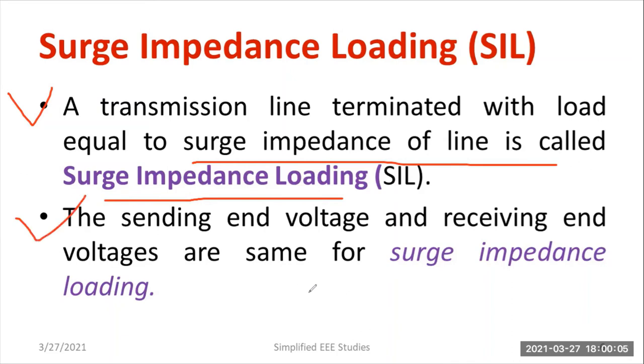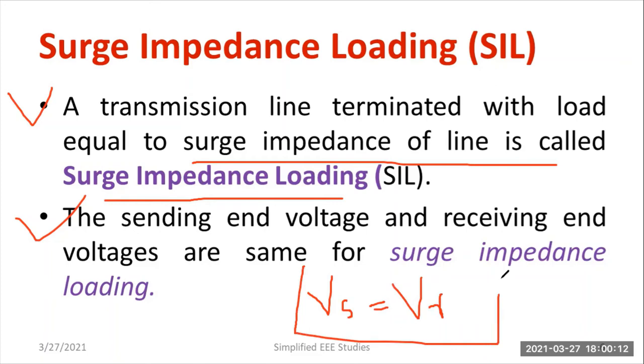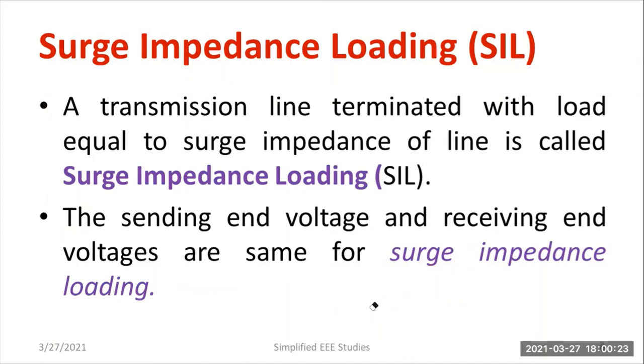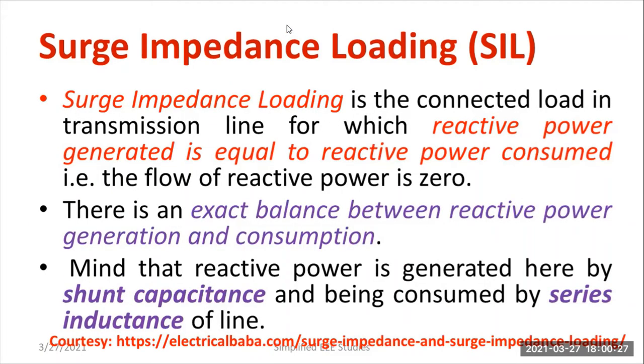In surge impedance loading, the sending-end voltage VS and the receiving-end voltage VR are equal. This is mainly applicable for a lossless transmission line. Surge impedance loading is the connected load in the transmission line for which the reactive power generated by the capacitor equals the reactive power absorbed or consumed by the inductor, so the overall net reactive power flow is zero.